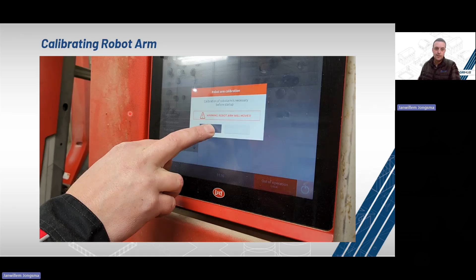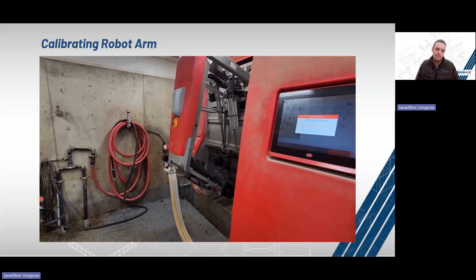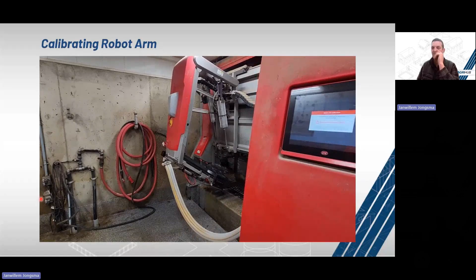So here's how you do it. Another maintenance item that often is forgotten is the arm calibration. On an A4, this is a little more important than on an A5, as the A5 does auto calibrations and the A4 will not do that. The importance of calibration is, in the first place, that the connection attempts will be affected by it. Secondly, it will also affect the wash performance. If the arm is out of calibration, it will not align properly under the jetters.